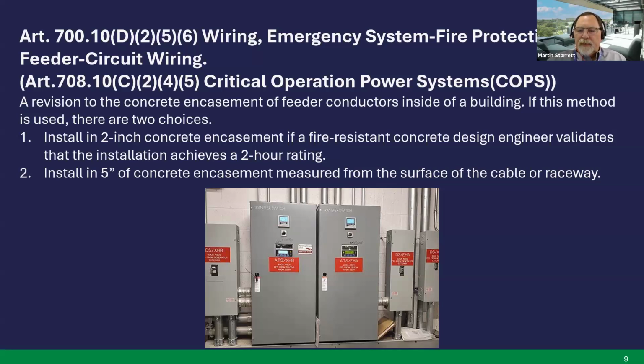But there's other methods besides concrete encasement. A few of those would be: the cable or raceway is installed in spaces or areas that are fully protected by an approved automatic fire protection system; the cable or raceway is protected by a listed electrical circuit protective system with a minimum 2-hour rating; or the cable or raceway is a listed fire-resistant cable system with a 2-hour fire rating. So there are some alternates to this, besides concrete encasement. Next slide.